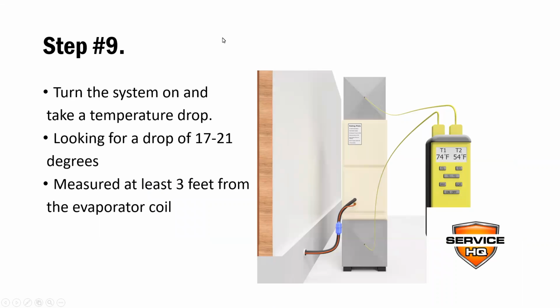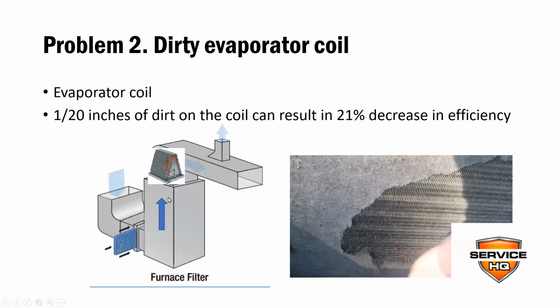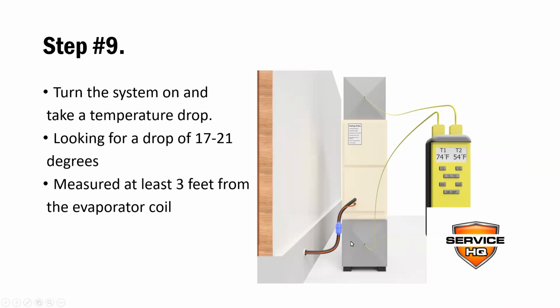Now, step number 9, turn the system on and we take a temperature drop, and we call it a delta T. We're looking for a delta T of 17 to 21 degrees. That just means temperature difference. So if we check the return air, this is an upflow, similar to the system that we just looked at in this slide. We've got our return right here. We're going to find out what our return is, and then we've got our supply coming out the top that feeds the cold air to all the rooms in the home. We're looking for a 17 to 21 degree temperature drop between the return and the supply.